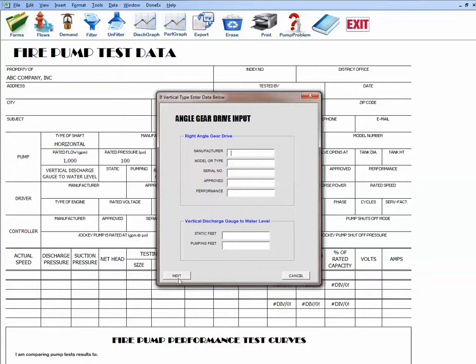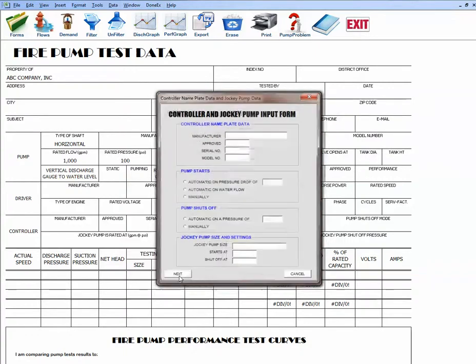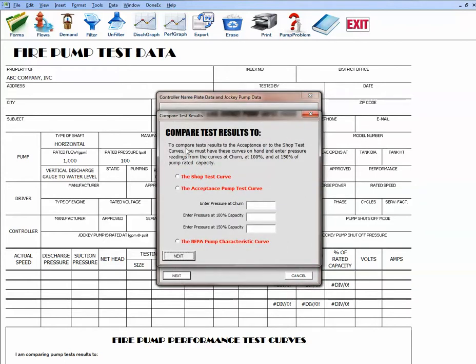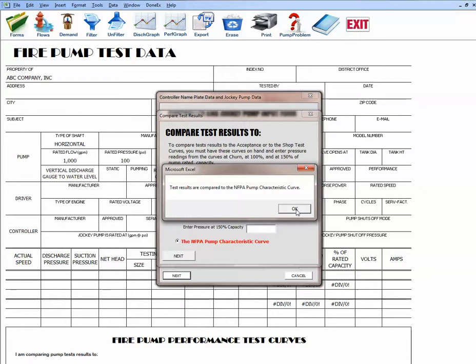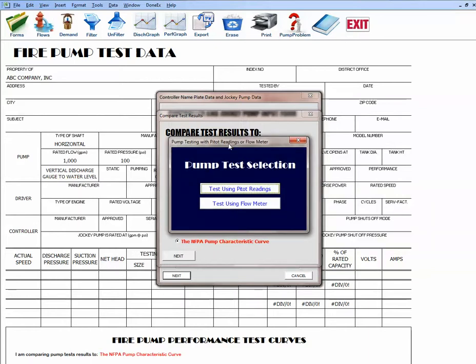Skipping additional fields, you can enter angle gear drive, pump driver information, and controller information. We then reach the point of selecting what to compare pump test data against. If you had a shop test curve or previous accepted pump test curve, you'd enter pressure at churn, 100%, and 150% capacity. Since we don't have a previous shop or accepted pump test curve, we select the NFPA pump characteristic curve to compare our test results against.